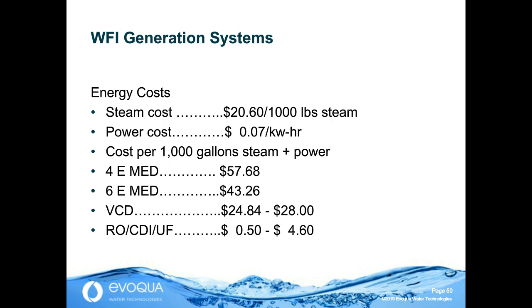But if you look at membrane, it could be as low as 50 cents a 1,000 gallons without water heating, depending upon water heating, motor efficiency, the type of electrodeionization device. Even with water heating, it is still going to be much lower typically than distillation.